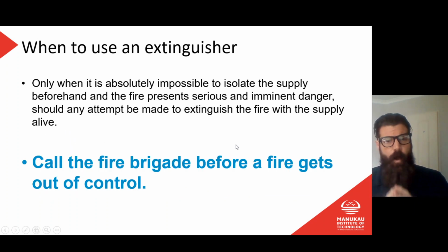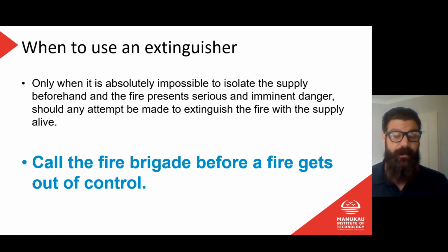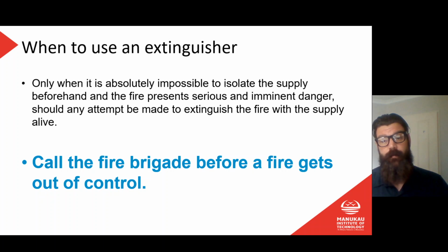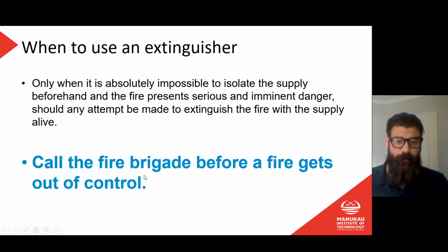When to use an extinguisher? Only when it is absolutely impossible to isolate the supply beforehand and the fire presents serious and imminent danger, should any attempt be made to extinguish the fire with the supply alive. So in any case that we want to fight a fire on electrical equipment, we should try and turn that thing off. If we can isolate the supply before we start to attack the fire, we definitely should do that. We should only attack that fire if we absolutely have to. And don't forget to call the fire brigade before the fire gets out of control. If you're going to go up and fight that fire, then maybe get somebody else to call the fire brigade while you're doing that.